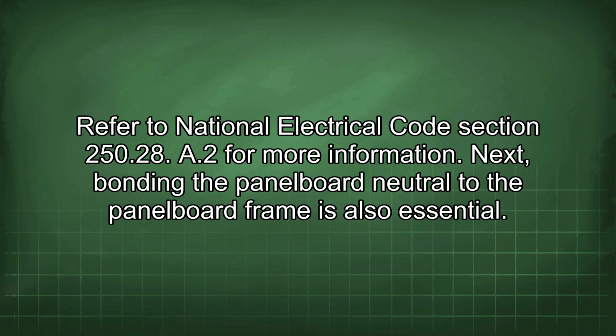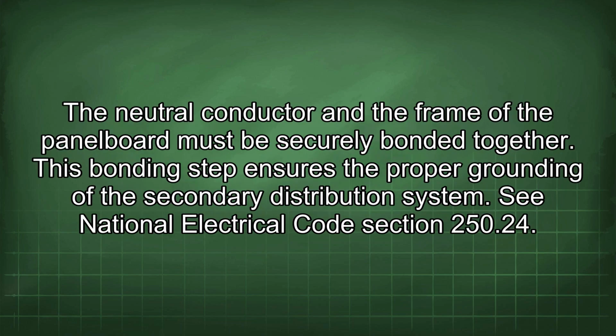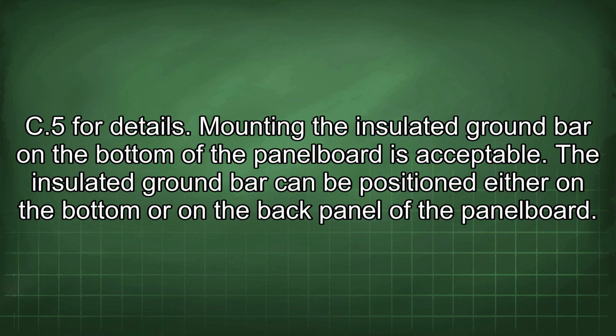Next, bonding the panel board neutral to the panel board frame is also essential. The neutral conductor and the frame of the panel board must be securely bonded together. This bonding step ensures the proper grounding of the secondary distribution system. See National Electrical Code Section 250.24 C5 for details.